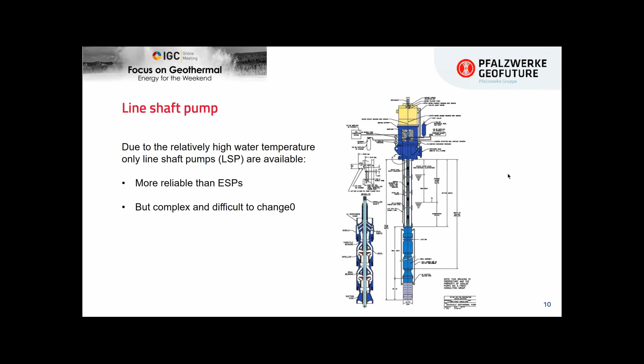Our pump, a 39-stage centrifugal pump, is installed at a depth of 750 meters in the borehole, and therefore we need a very long driving shaft of the same 750 meters depth. So you can imagine a pump workover, or pump exchange, is a very intense operation, usually taking a couple of weeks to complete.